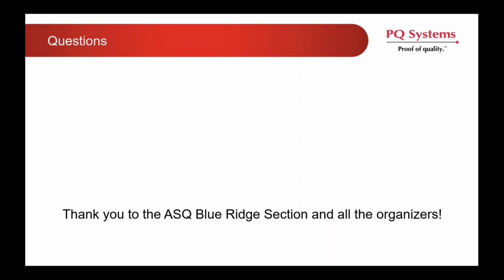The first question that I see being asked is what software is being used in your examples? The software we're using in the slides is PQ Systems software called GAGEpack. It'll do the calculations for you, but you can accomplish these studies without software. You can do it by hand. I've done them numerous times. It's a big time waste. Even when I know what the results should be, I still make mistakes. So having software like GAGEpack, or really if you want to do it in Excel, that's fine. Other programs are also fine. The big ticket there is you hit compute and let the program do the work, and now you're just focusing on the setup, the conducting of the experiment, and the analysis. So great question, thank you.